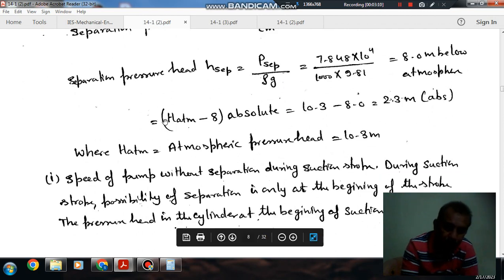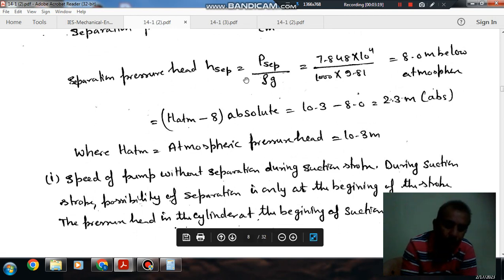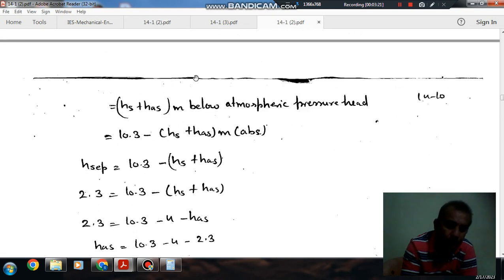At the beginning of the stroke, there is possibility that separation can occur at the minimum head. So at the beginning of the stroke, the head is Hs plus Has, where Hs is suction head and Has is acceleration head required in the suction stroke.